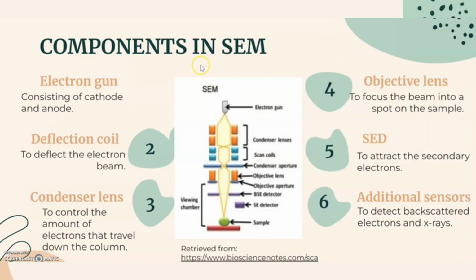The components in SEM that we need: first of all, we need an electron gun that consists of a cathode and anode, a deflection coil to deflect the electron beam, a condenser lens to control the amount of electrons that travel down the column, an objective lens to focus the beam into a spot on the sample, an SED to attract the secondary electrons, and also additional sensors to detect backscattered electrons and X-rays.